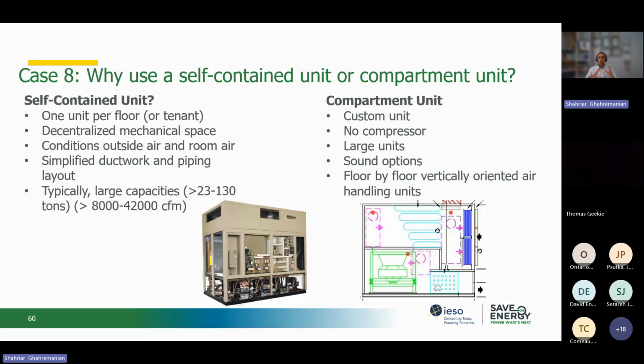So basically, we can have one of those units per floor, and these are decentralized mechanical systems. We can put these systems in a decentralized mechanical space, and then have a simplified ductwork or piping layout, which is a good thing to have. And then a compartment unit, which doesn't have any compressor, so the units are larger, but we are going to have sound if we install it nearby the office area.